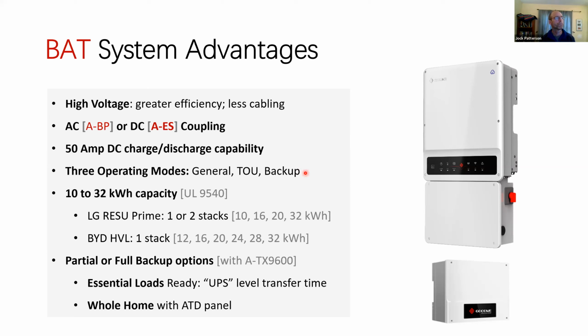Operating modes. If you're using a hybrid inverter or a battery-only inverter, you may be getting it just for backup and saying, I want this battery charged at 100%, keep trickle charging it, ready for an outage. However, while most people want that insurance there, that they've got backup, there are often opportunities to save money or even look at as making money by dealing with time of use rates, where you want to avoid consuming from the grid during peak time, so you consume from your battery. You can program the battery to just discharge at those peak periods. There's a few other options there, like export limitation, all falling under trying to control when you use your PV energy, not just when it's being produced, but being able to store it for when it's ideal to use it, including demand response programs that certain locations have.